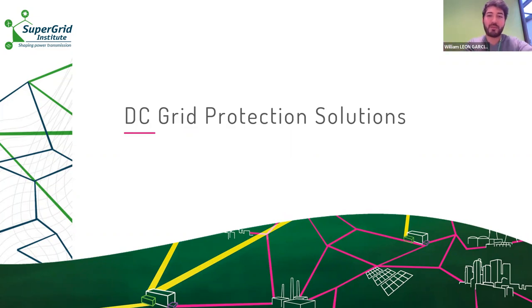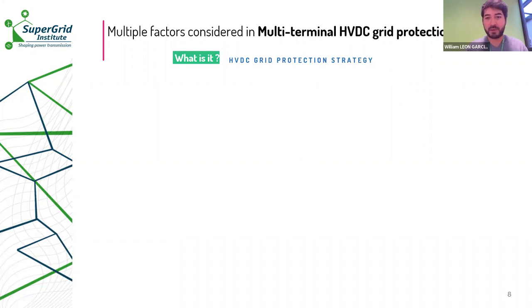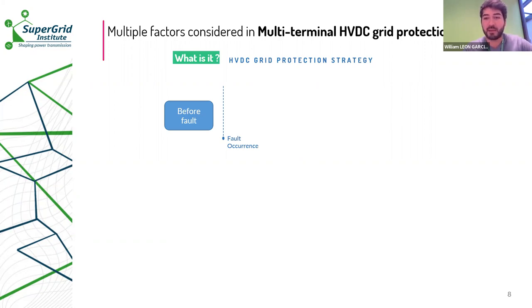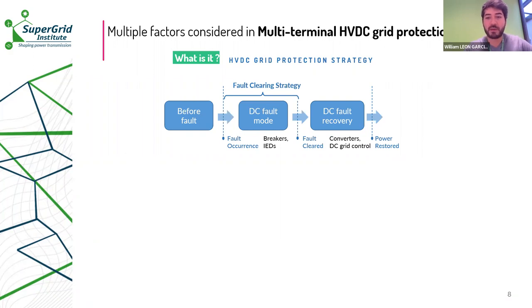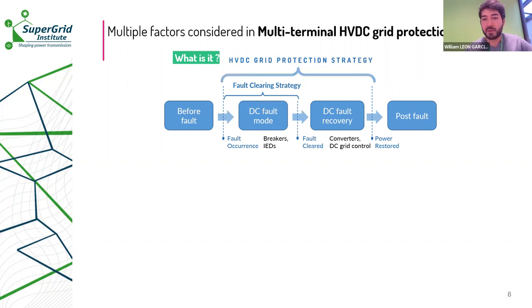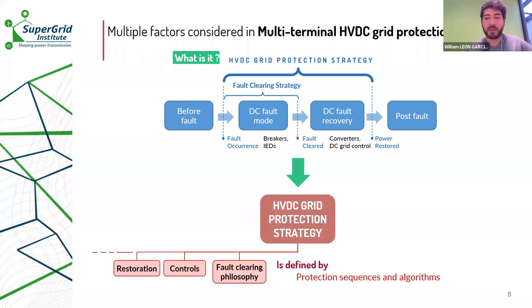How do we design protection for MTDC systems? When a fault occurs in an HVDC system, the first step is to clear the fault using intelligent electronic devices called IEDs and DC breakers — this is called the fault clearing strategy. Once the fault has been cleared, it is important to restore the grid voltage and power through the MTDC converters via coordination and recovery actions. After the fault, we find a new operating condition with one element less — the faulty element now isolated. The grid protection strategy encompasses both fault clearing and recovery actions, defined by sequences and algorithms run in relays.